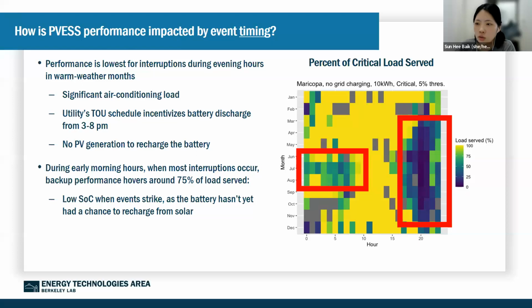Also, as noted earlier, most interruptions in Maricopa occur during early morning hours in July and August. Backup performance during those hours typically hovers around 75% of the load served, as the battery has limited charge before sunrise. This suggests that reserving more power for year-round evening and summer morning outages could be beneficial in mitigating the impacts of power interruptions.